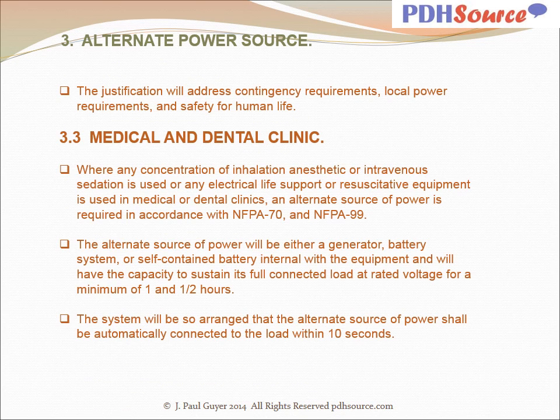The justification will address contingency requirements, local power requirements, and safety for human life. For medical and dental clinics, where any concentration of inhalation anesthetic or intravenous sedation is used, or any electrical life support or resuscitative equipment is used in medical or dental clinics, an alternative source of power is required in accordance with NFPA 70 and 99. The alternative source of power will be either a generator, battery system, or self-contained battery internal with the equipment and will have the capacity to sustain its full connected load at rated voltage for a minimum of 1.5 hours.